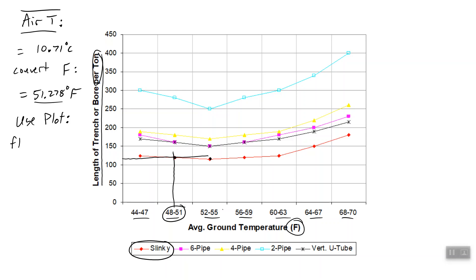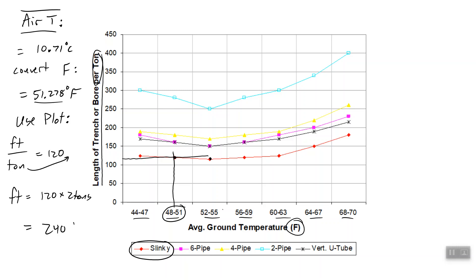So the feet of trench per ton of cooling is equal to 120, which means the feet of trench that we have to dig is 120 times 2 tons. I just moved this up here and multiplied by the number of tons, which gets me 240 feet. 240 feet of trench. That is our answer. Okay, thank you for watching.